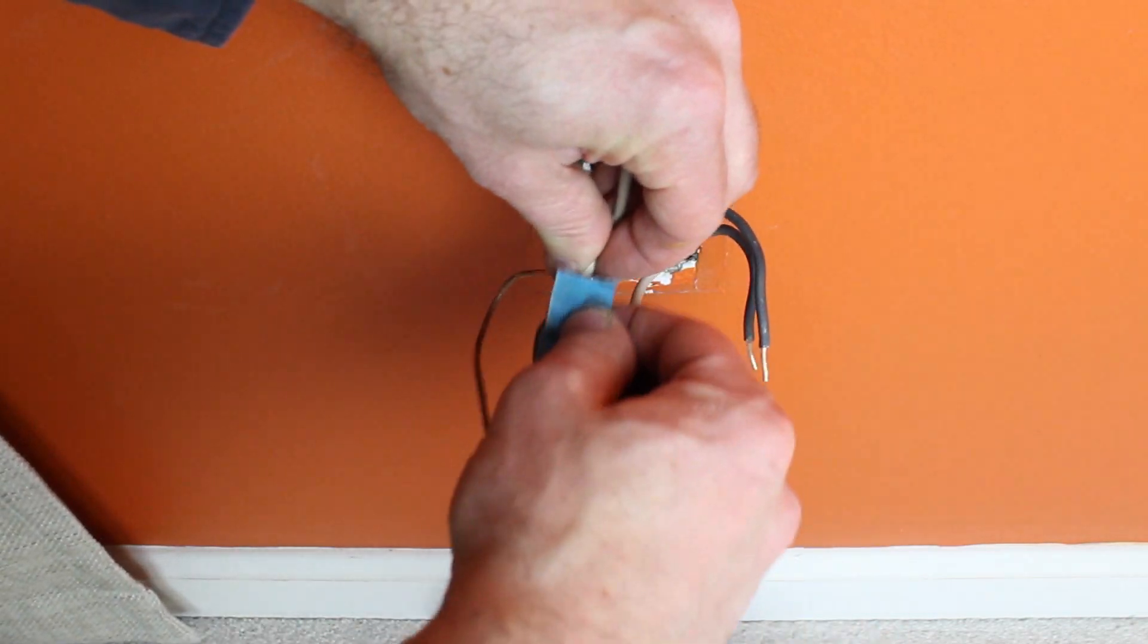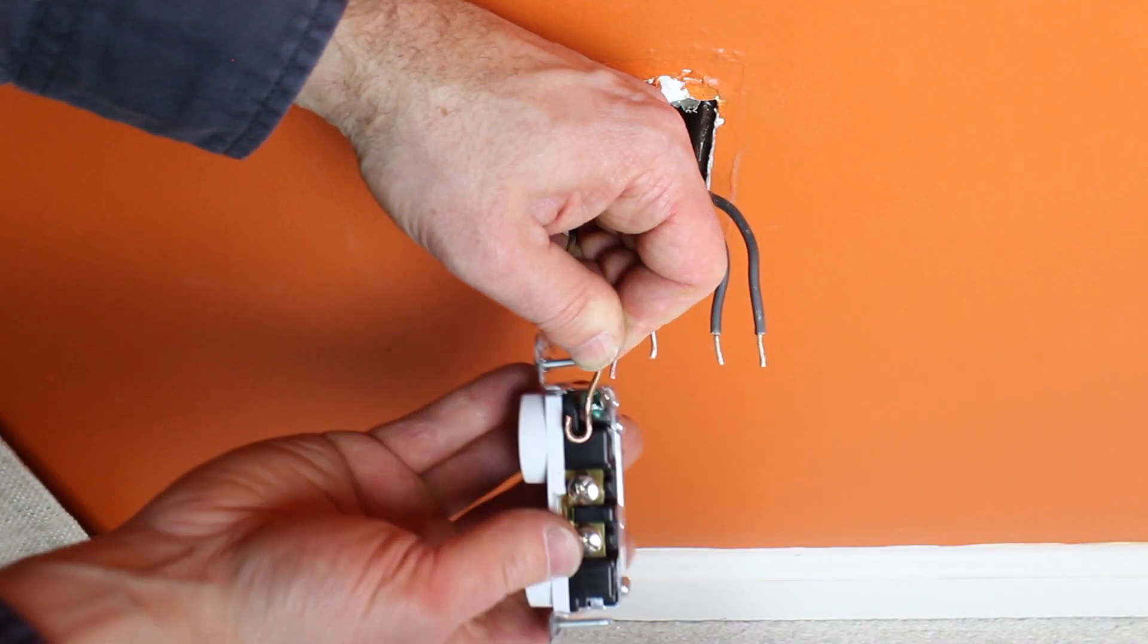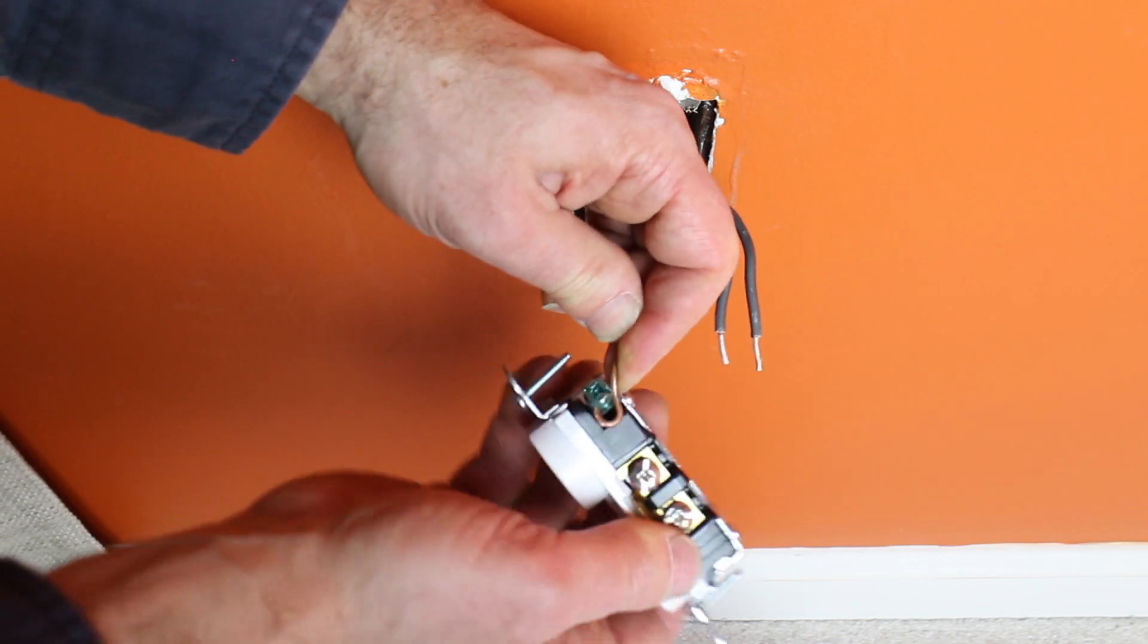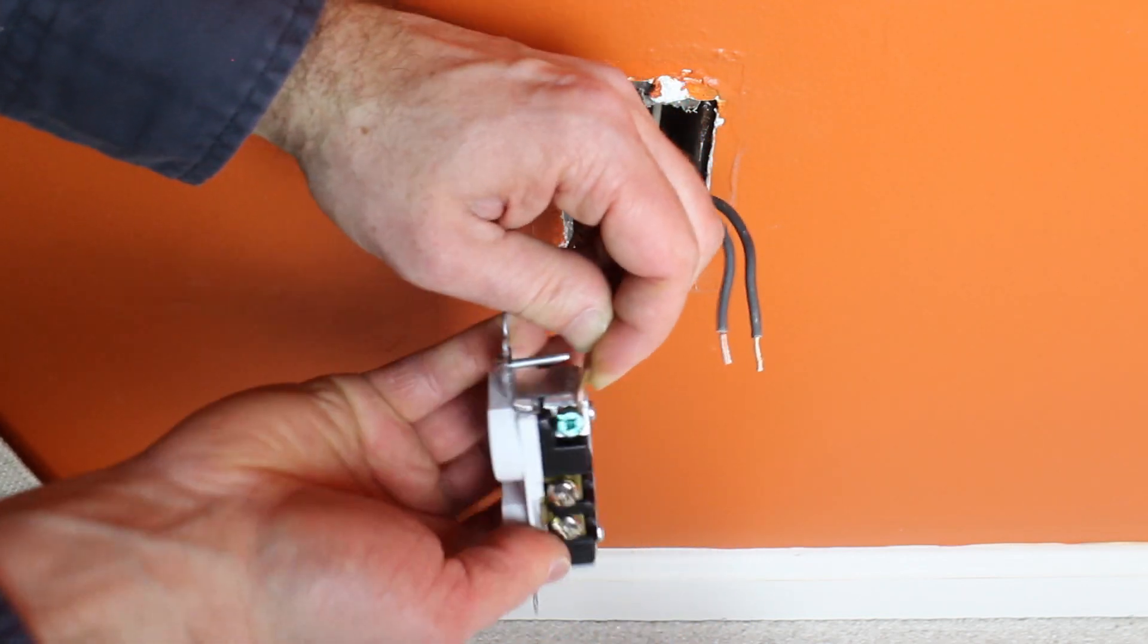Wire up the ground wire first to the green terminal screw. Make sure it's looped around clockwise and then tighten down that green terminal screw.